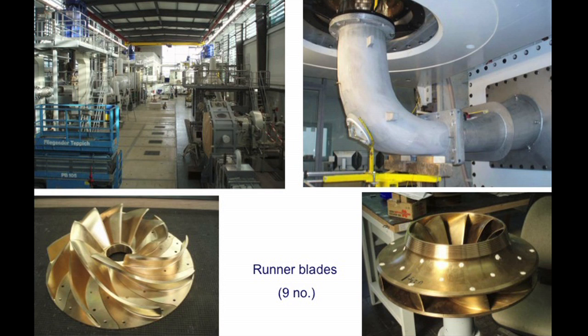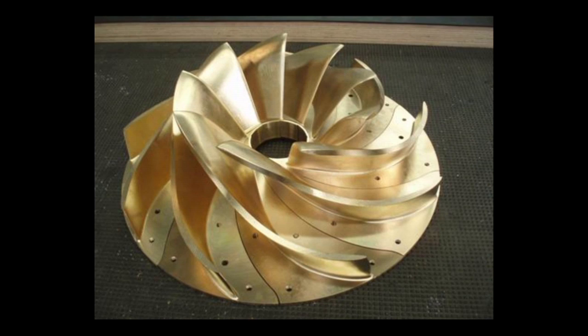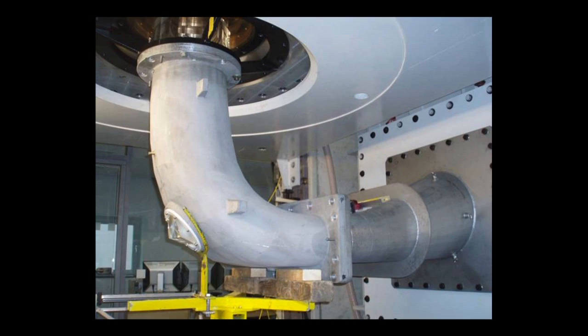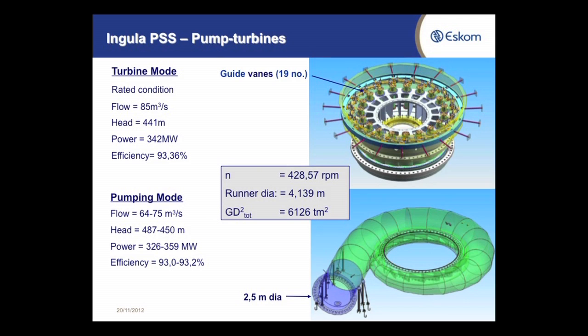If you design a runner for such a big scheme, you can't buy them off the shelf. They first do a CFD analysis and determine the runner blades, the number of runner blades, the size of the blades, and from that they build a model out of copper. That model was about that size, about 400 millimeters. The real size is 4.2 meters, so it's about 1 in 10 scale, roughly. And then we tested that model in a test apparatus. You can see the model there. There's a glass cover there. You can see how the water flows through the model. And from that you determine what the efficiencies are.